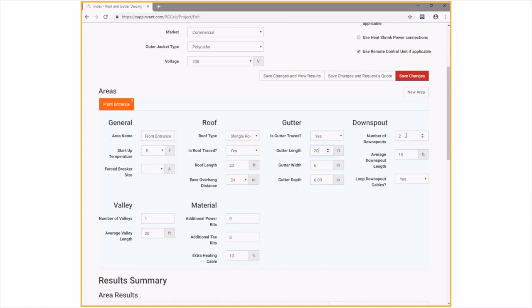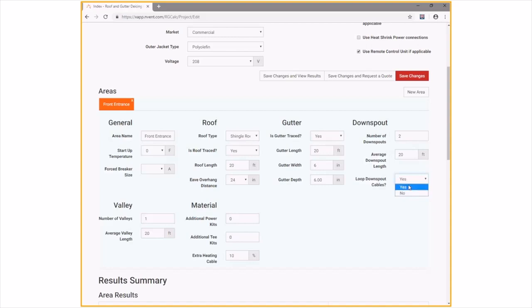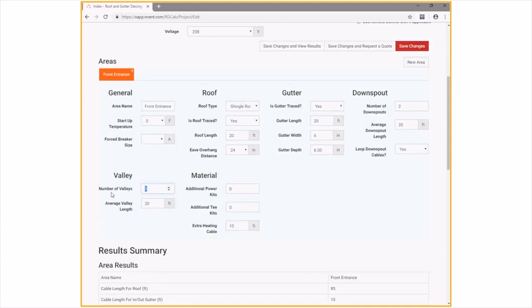When considering downspouts, you can choose to loop the heating cable or, if you select no loop, the system will include a T at the top of the downspout. Looping is recommended for downspouts 20 feet or shorter or those 4 inches or greater in diameter. Since this front entrance has no valleys, I'm zeroing that out. Remember: when entering a valley, input the full valley length — the calculator automatically uses two-thirds of that length per the design and installation manual.